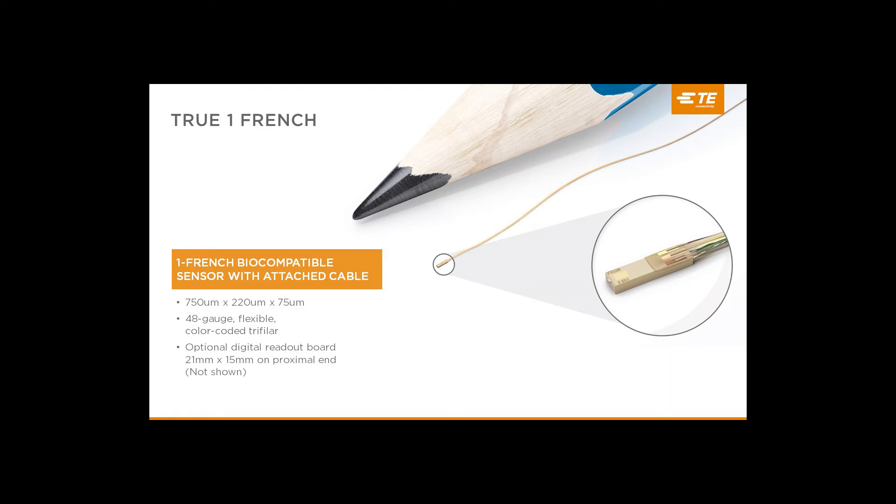IntraSense consists of, at minimum, a silicon-based pressure sensor, a three-stranded cable, and encapsulation over the cable-to-sensor junction. Optionally, you can also have a PCB on the proximal side. This performs temperature compensation and some other features. Starting with the sensor — five of these sensors could rest comfortably inside a square millimeter. They're 750 microns long, 220 microns wide, and 75 microns thick. When you connect the wires on top and add the encapsulant, the total thickness is going to be about 170 microns. This means they can be mounted inside a one French hypo tube. The wires connected to the sensor are AWG 48 gauge, available in lengths between 60 and 300 centimeters. The optional PCB calibration board is 21 by 15 millimeters.